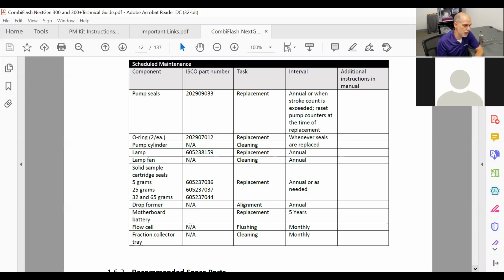This says monthly. I would almost flush your flow cell twice a month, depending on how much you use it. If it's a daily device for you, if you're using it anywhere from 4 to 8 hours a day, every day, flush it twice a month. I like to flush it with methanol because I have it so readily available. Acetone, though, is a great solvent to use. Flush it through your whole system. It'll get rid of any sample that may be hardening into like a crystalline.